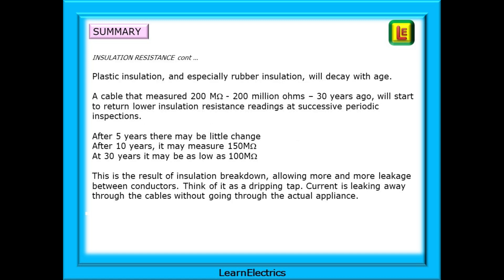And what happens to the plastic insulation with age? Plastic insulation, and especially rubber insulation, will decay over the years. A cable that was measured at 200 mega ohms - 200 million ohms - 30 years ago will start to return lower insulation resistance readings at successive periodic inspections. After 5 years there may be little change. After 10 years it may measure 150 mega ohms. At 30 years it may be as low as 100 mega ohms. This is the result of insulation breakdown allowing more and more leakage between conductors. Think of it as a dripping tap - current is leaking away through the cables without going through the actual appliance.